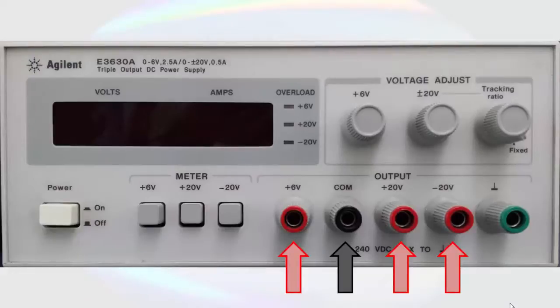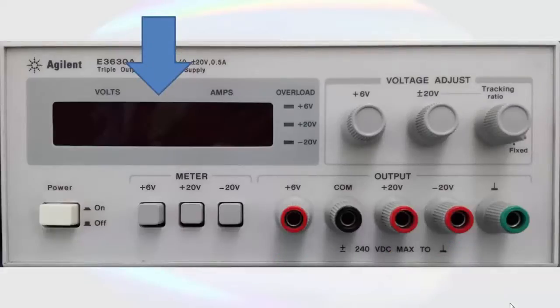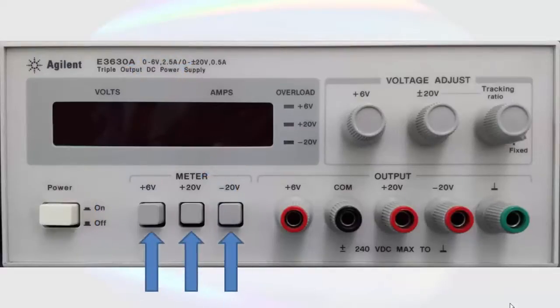Let's briefly go over the rest of the front of the display. Here we have the power supply's display. This will display the electric potential in volts and the current in amps of whichever channel is selected by the meter buttons. The meter buttons do not affect the output voltage of the supply. They only change what is displayed on the indicator.